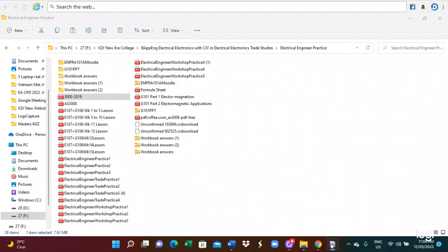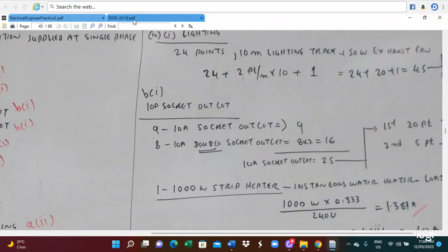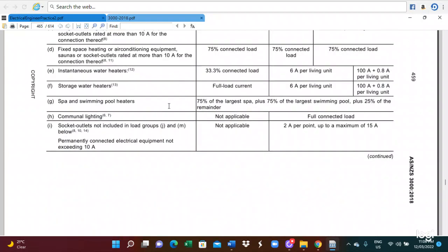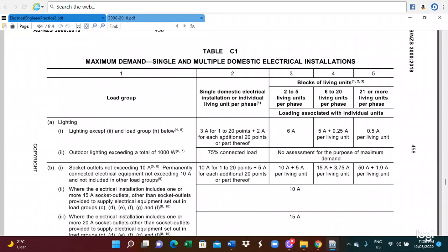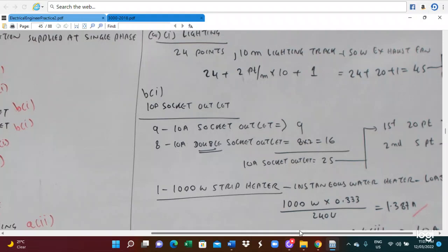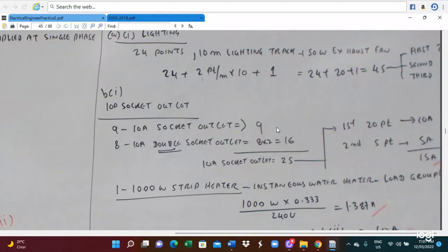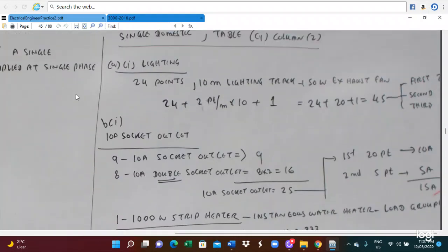Because of the 45 points, we have to count the load group A1. So how many points are there? Every 20 points you have to count 3 ampere. So 45 is equivalent to 20 plus 20 plus 5. The first 20 points, 3 ampere. The second 20 points, 3 ampere. And the additional 5 points, we add 1 ampere. So how much current will there be? The first 20 points is 3 ampere, the second 20 points is 3 ampere, and the final 5 points is 1, so this is 7 ampere. So this is the way we calculate it. The maximum demand is 7 ampere. Okay, this is how we calculate the maximum demand.